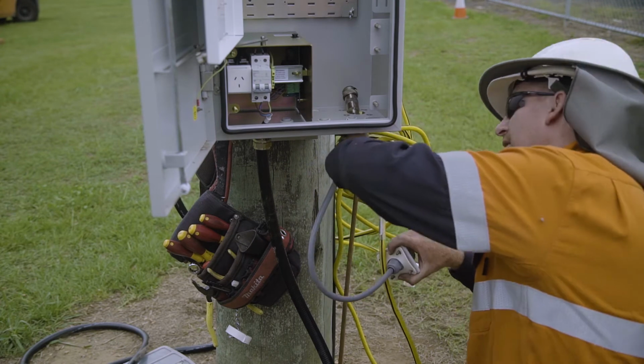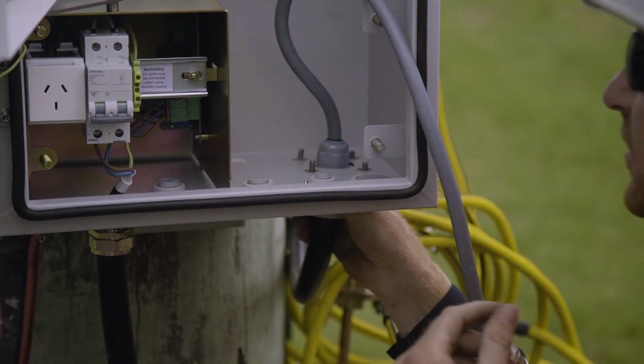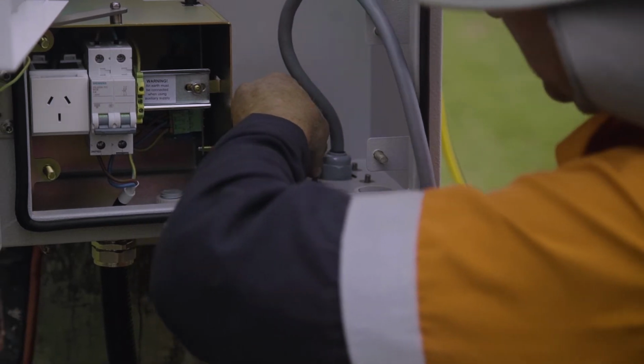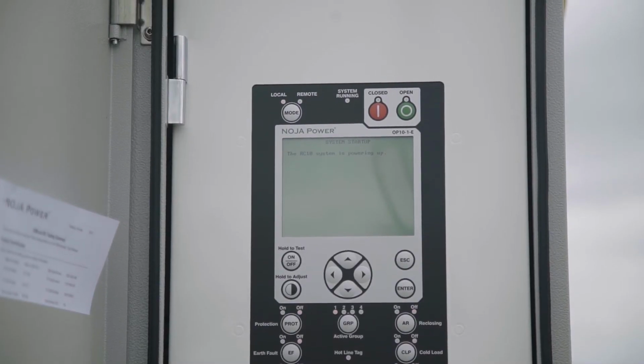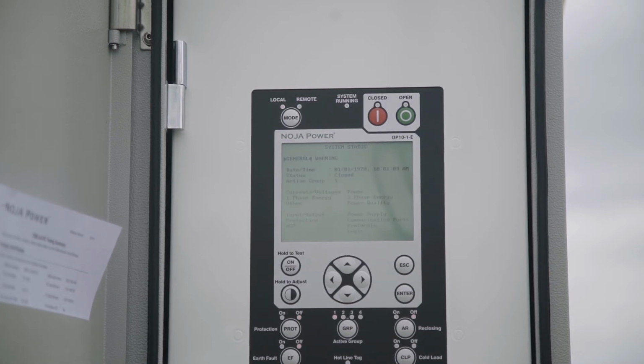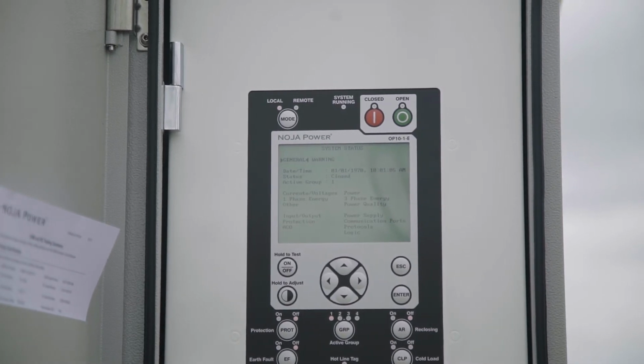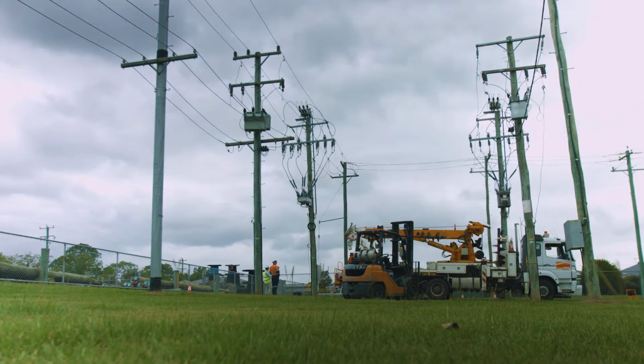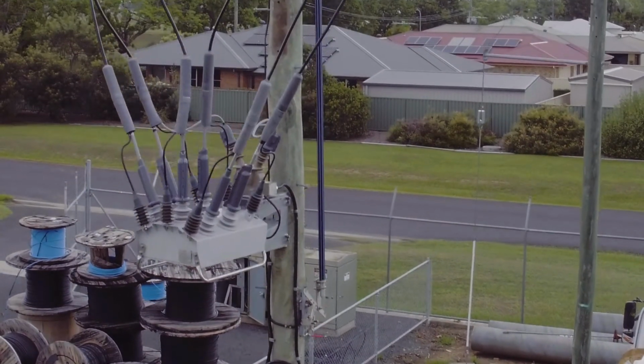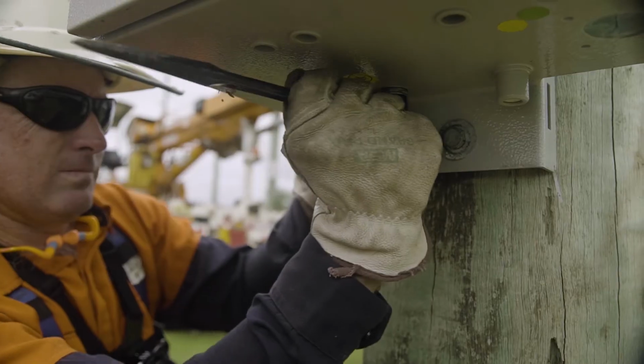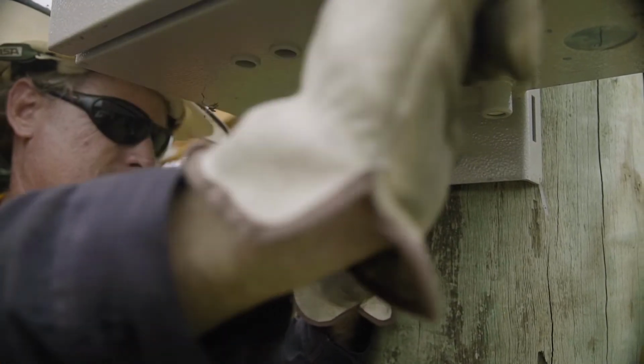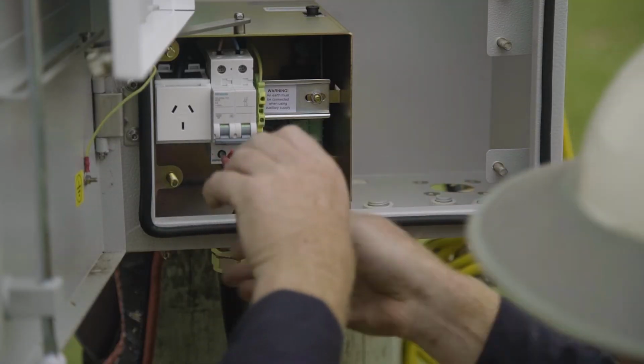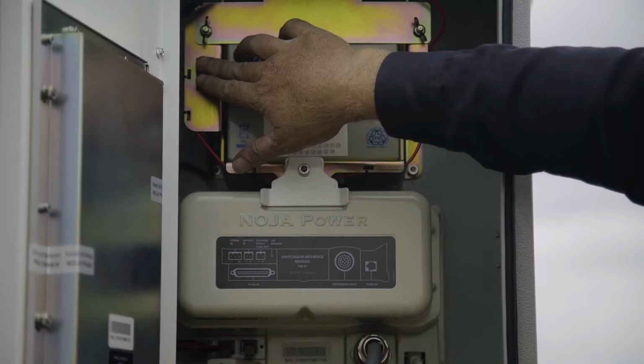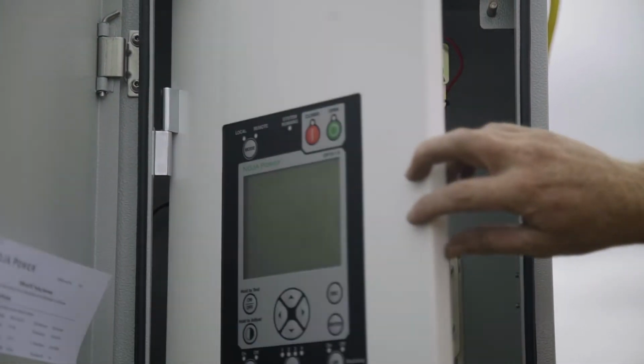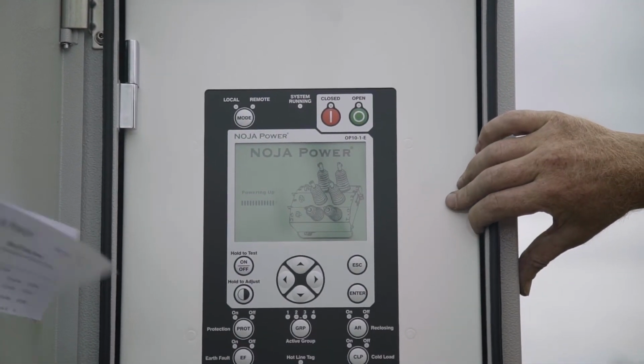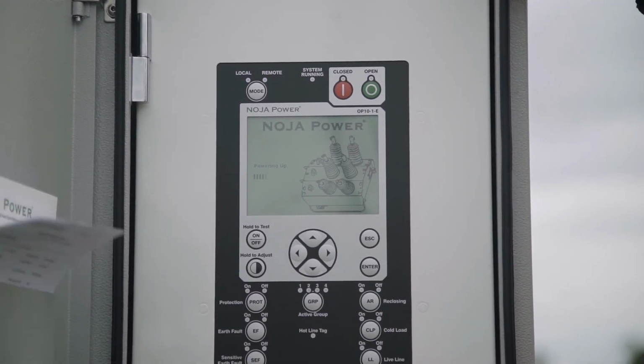All cables taken into the RC10 must be sealed and secured with glands to maintain the IP rating of the cubicle. It's best practice to confirm voltage and current is present and within the expected ranges once the bypass switch has been opened. The installation should be checked before final commissioning. Check that all the HV connections have been tightened and inspect the earth wiring and confirm it's been connected as specified in the user manual. Inspect the LV wiring is complete and connected safely. Check the LV supply is on. If possible, conduct some manual trip and close operations from the panel to confirm operation.